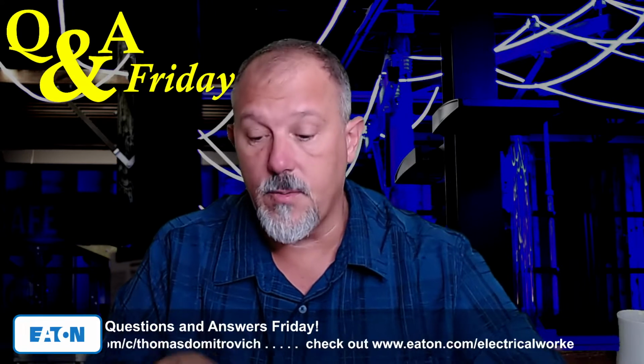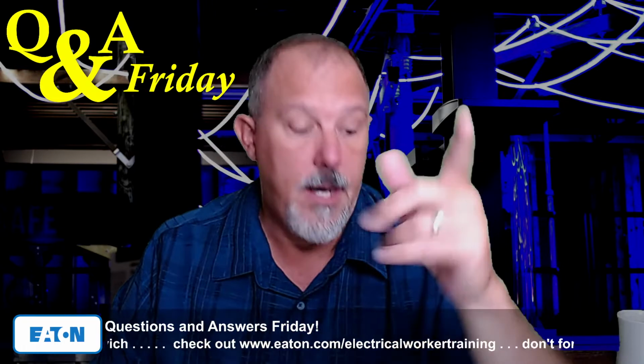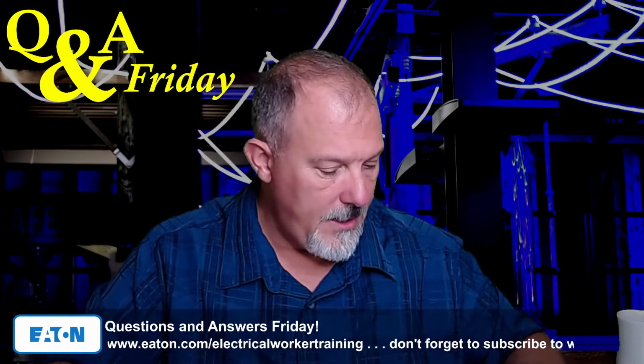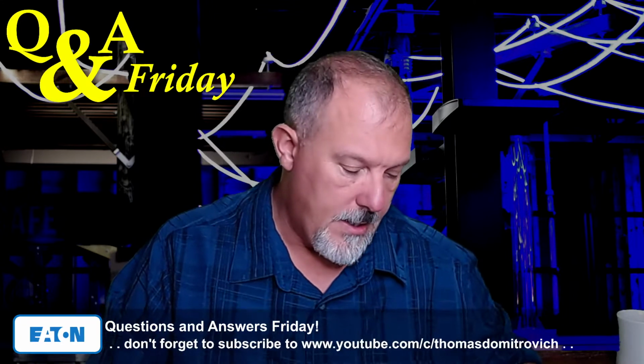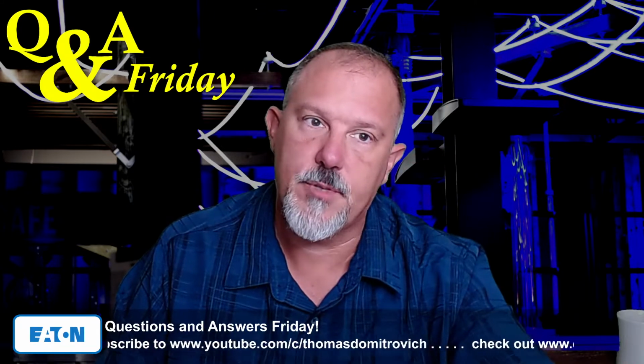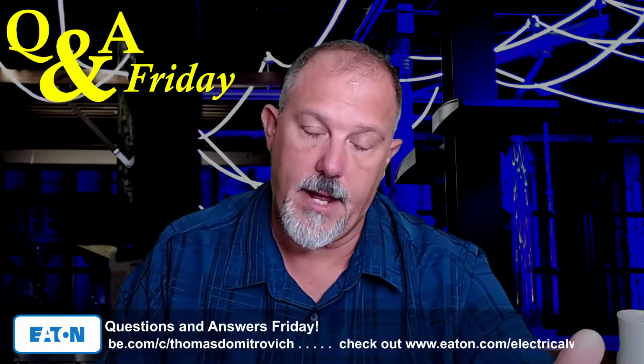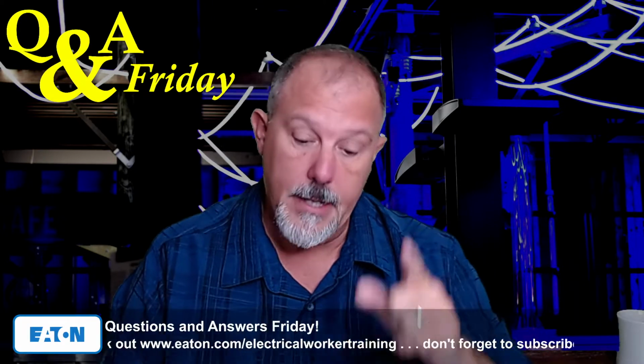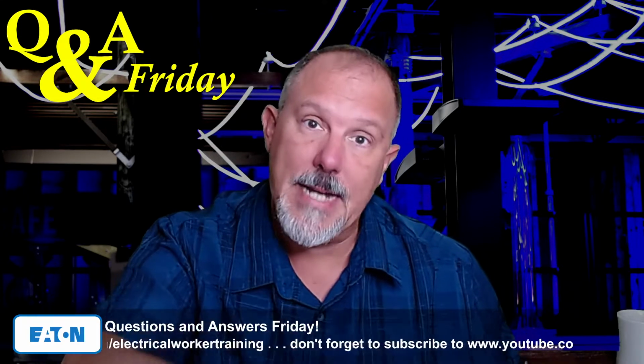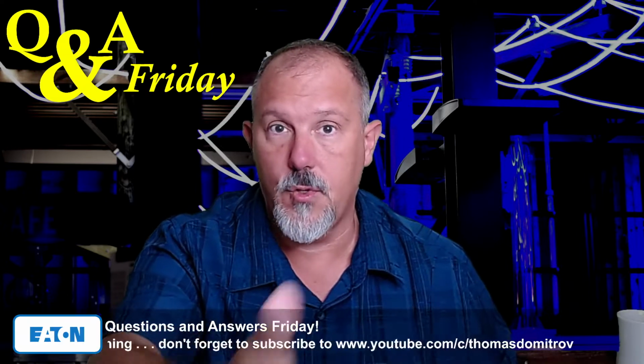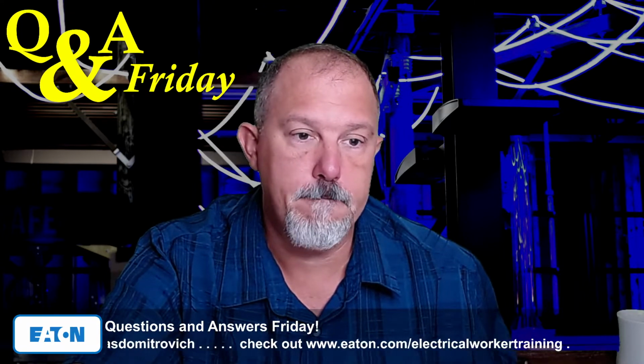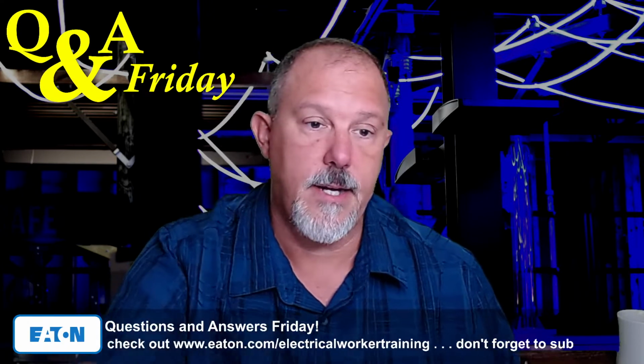Now, in the 2023 cycle, we're taking GFPE down to 800 amps. You'll notice in 110 for working space, we went from a working space driven off of a 1200 amp service device to, if you add up those devices and they equal 1200 amps, now you need to have that extra door. So they're making changes there, realizing what people are doing, to your point, JW. So 240.87 is moving down to 1000 amps, and we almost passed down to 800 amps during our code cycle, but I think Alan Manche and another on the panel pushed back and said, we can go for that, but we need a delay. So I don't disagree with you. People will change their designs, and it's unfortunate.